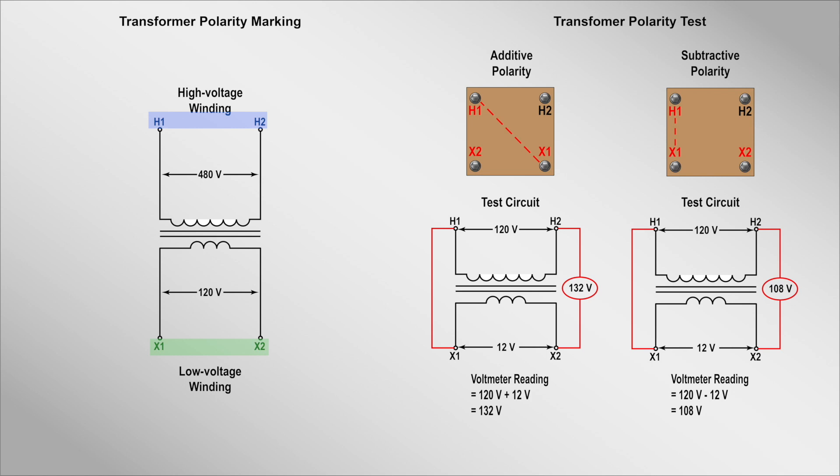By convention, H1 and X1 have the same polarity. This means that when H1 is instantaneously positive, X1 is also instantaneously positive. Transformers can either have additive or subtractive polarity. What this refers to is the location of the H and X terminals as they are brought out of the transformer's case. Looking at the drawing, when X1 is diagonally from H1, the transformer is said to have additive polarity, and when X1 is directly across from H1, then the transformer has subtractive polarity.